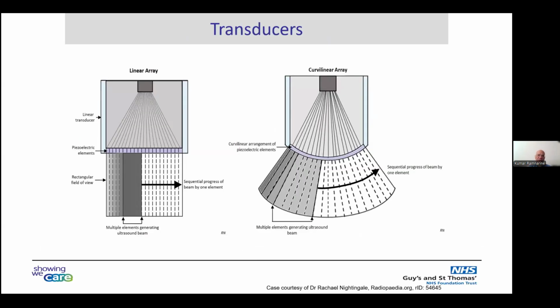They sweep across the scan plane in order to produce the image. On the left is a linear array transducer, and on the right is a curvilinear array transducer. Those are the two most common types of modern diagnostic transducers today.